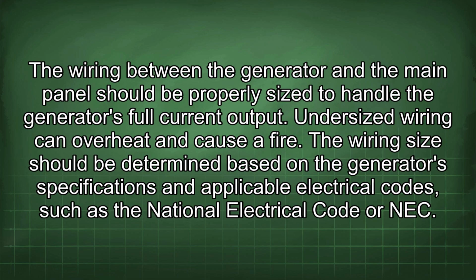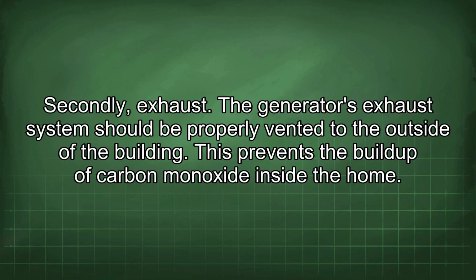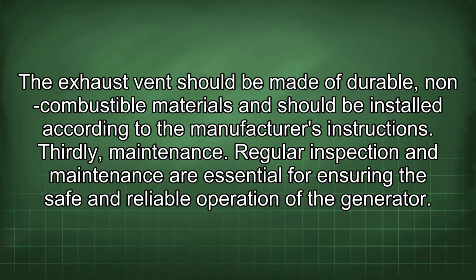Firstly, wiring. The wiring between the generator and the main panel should be properly sized to handle the generator's full current output. Undersized wiring can overheat and cause a fire. The wiring size should be determined based on the generator's specifications and applicable electrical codes such as the National Electrical Code or NEC. Secondly, exhaust. The generator's exhaust system should be properly vented to the outside of the building. This prevents the buildup of carbon monoxide inside the home. The exhaust vent should be made of durable, non-combustible materials and should be installed according to the manufacturer's instructions.